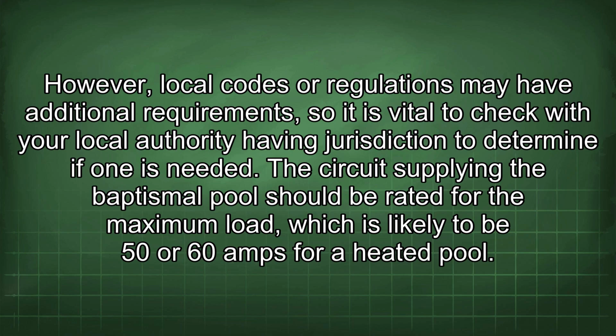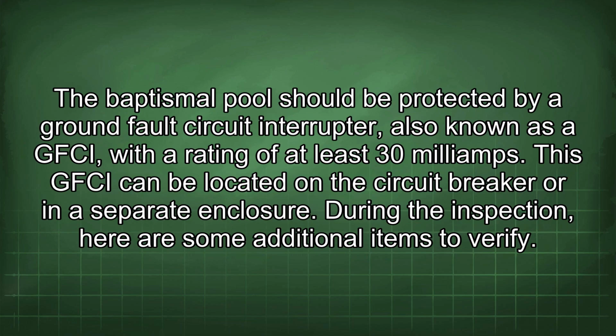The circuit supplying the baptismal pool should be rated for the maximum load, which is likely to be 50 or 60 amps for a heated pool. The baptismal pool should be protected by a ground fault circuit interrupter, also known as a GFCI, with a rating of at least 30 mA. This GFCI can be located on the circuit breaker or in a separate enclosure.